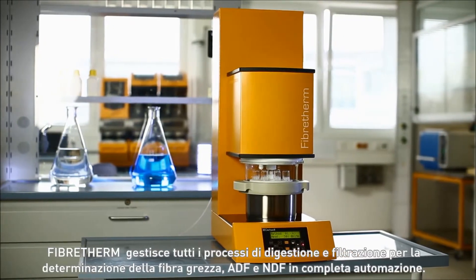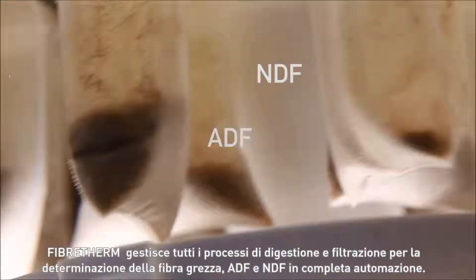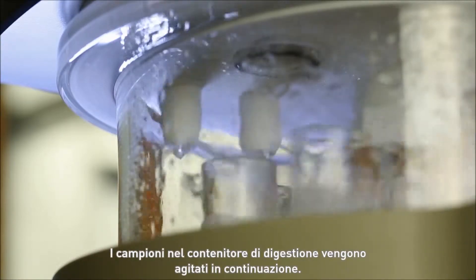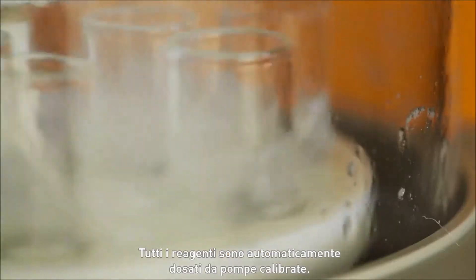Fibretherm handles all digestion and filtration processes for the determination of crude fiber, ADF and NDF fully automatically. The samples in the digestion vessel are continuously agitated, and all detergents are automatically dosed by calibrated pumps.